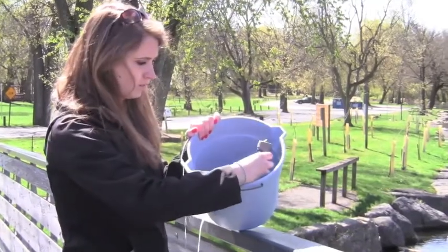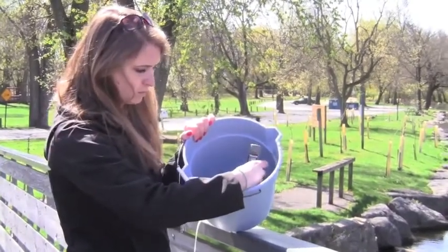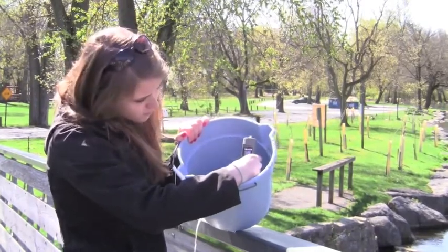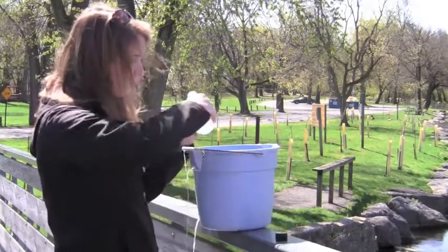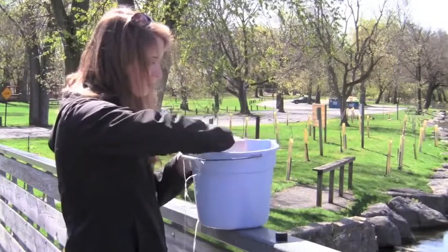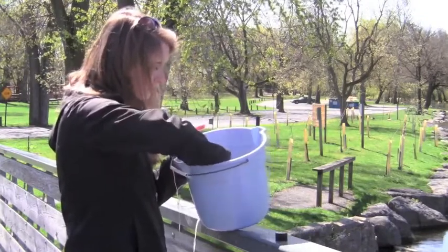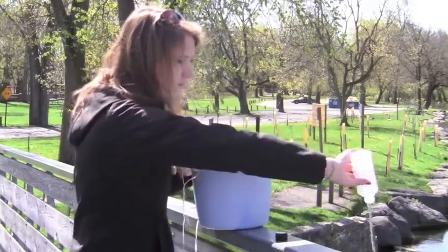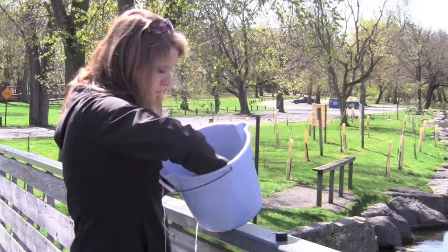Take your conductivity and TDS measurements with your meter directly from the bucket. Once again, refer to the instructional meter video if you're unsure how to do this. You can also take the water sample directly from the bucket. Once again, you take your sample the first time you monitor, and then again if you notice a spike of 3 times or more in your conductivity or TDS measurements at a comparable flow. Be sure and rinse the bottle 3 times. Then fill a sample bottle with water.